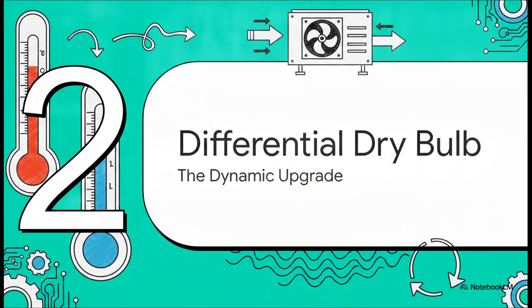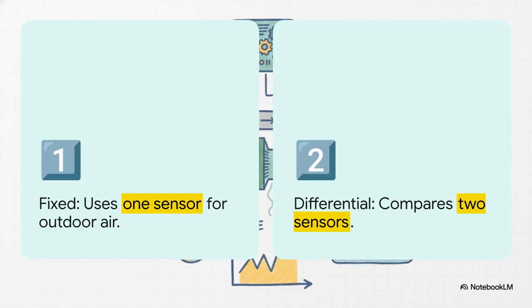So to fix those rigid limitations, engineers came up with method number 2, the differential dry bulb strategy, otherwise known as the dynamic upgrade. Now, adding a second sensor totally changes the game here. While the fixed strategy only looks outside, this differential strategy slaps a second sensor on the return air coming from inside the building. This lets the system compare the two and make dynamic, real-time choices based on actual indoor conditions. It basically just asks one question: is it cooler outside than it is inside? If yes, open the vents.